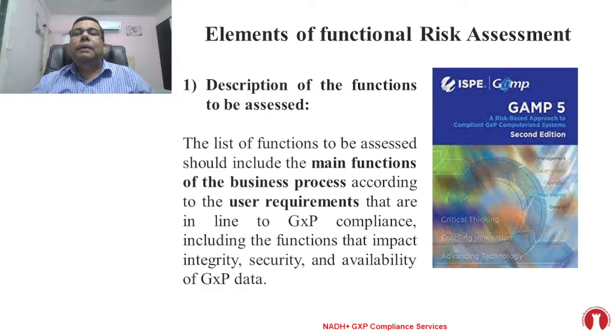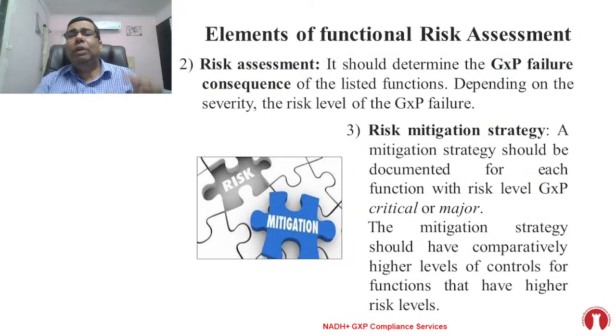The functional risk assessment first stage is description of the function to be assessed. You have to identify the functionalities of that particular control you need to assess, like operation of some actuator valve, operation of other valves, operation of some cooling mechanism, or operation of alarms. All these functionalities you need to enlist as part of functional risk assessment stage 1. This is specified in the slide, you can go through it in detail. I'm explaining in simple language so you understand PLC validation easily.